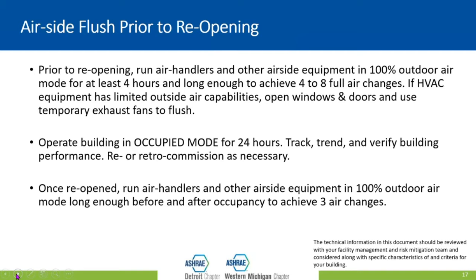And finally, you want to do a daily flush once the building is reoccupied, at least 2 hours after occupancy, or however long it takes to achieve 3 air changes, to ensure that you've got good clean air, because the air may have been breathed in, right? It's been contaminated. People have coughed and talked and sneezed in that air. And you want to make sure that you exhaust all of that so that you have a stable, clean, acceptable air to start off your next occupancy cycle.